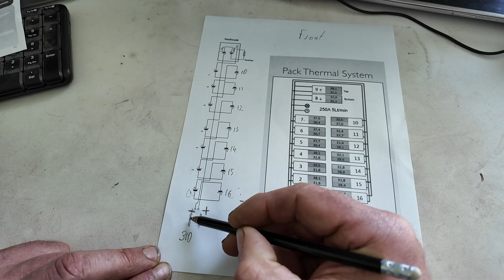So again, we measured 310 on the negative contactor, and we measured 44 volts on the positive. As we calculated, 44 divided by 22 is 2 modules.